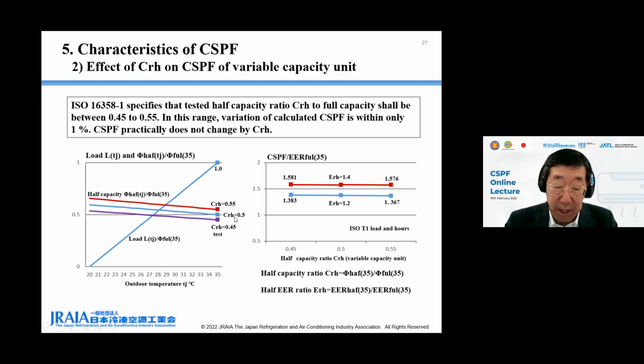The right figure shows CSPF divided by 35 degrees C full EER for half capacity ratio CRH from 0.45 to 0.55. Half EER ratio Erh of the example are 1.2 and 1.4, which correspond to lower and upper sides of the usual range in laboratory tests. For both ERH 1.2 and 1.4, variation of CSPF by half capacity ratio CRH is within only 1%. CSPF practically does not change by half capacity ratio CRH in the ISO specified range from 0.45 to 0.55.